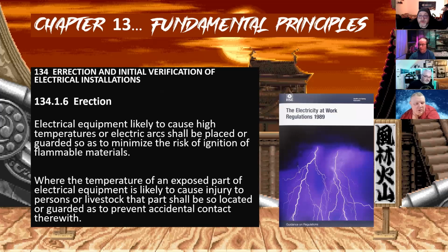John, yep, it is. So 134.1.6: electrical equipment likely to cause high temperatures or electric arcs shall be placed or guarded so as to minimize the risk of ignition of flammable materials. Again, that's shall. Where the temperature of an exposed part of electrical equipment is likely to cause injury to persons or livestock, that part shall be so located or guarded as to prevent accidental contact therewith.